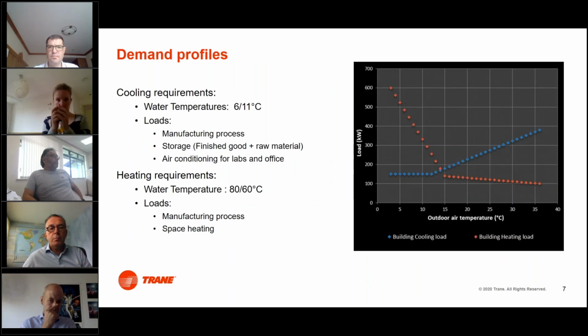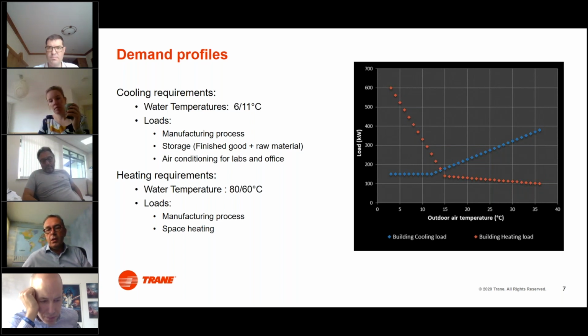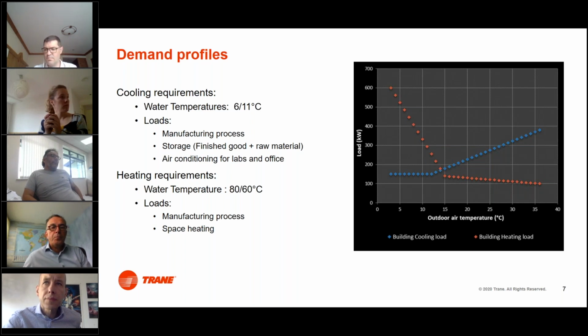Looking at the profile of the process, it looked a little bit like a comfort cooling process, but there were constant cooling requirements, and there were at winter time. You can see that this was southern France, so between 0 and 10 degrees, there was still cooling requirement there, and also at summertime there was still heating requirement in the same plant for the process applications. The heating temperatures that were required were about 60 to 80, and the cooling requirement required were 11 to 6.